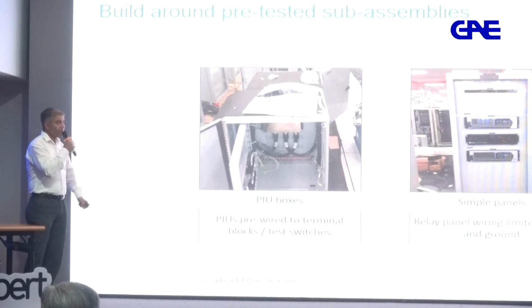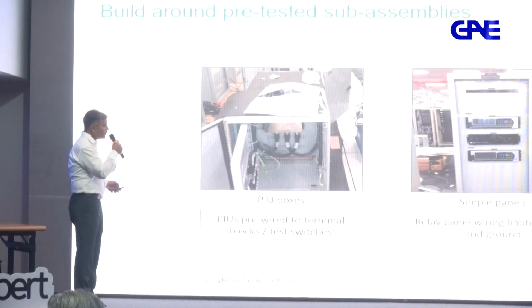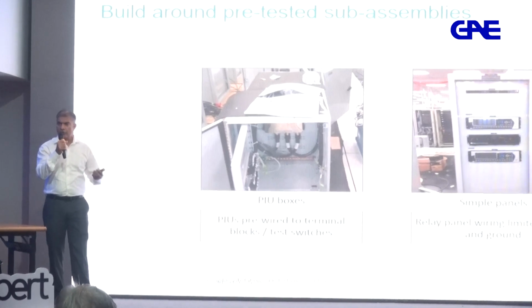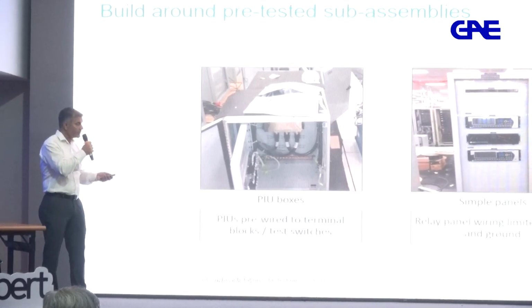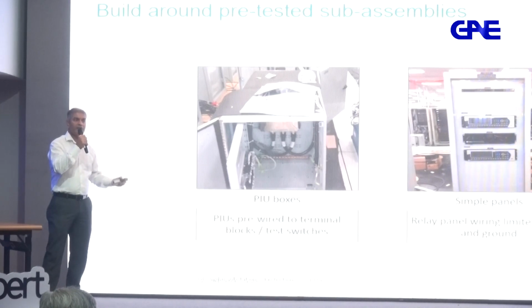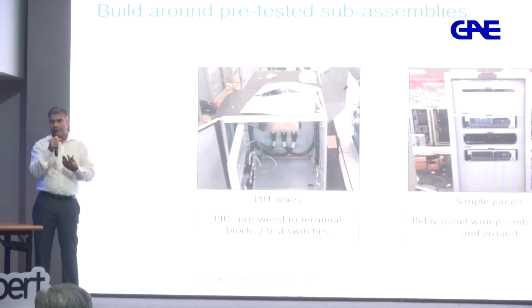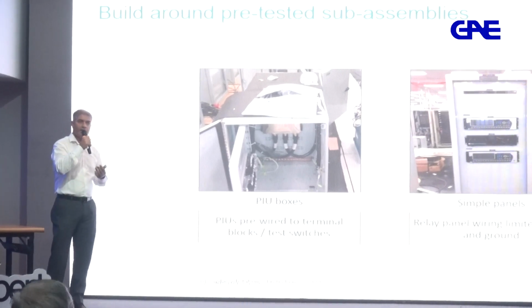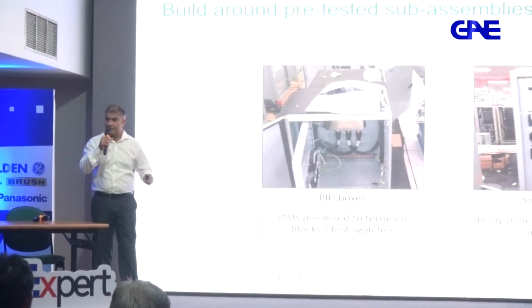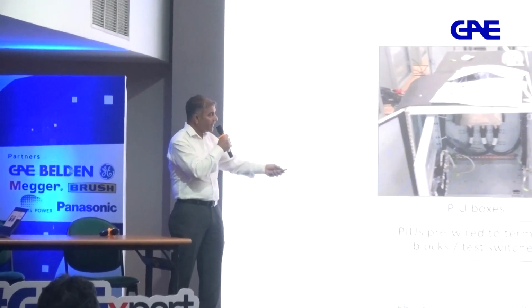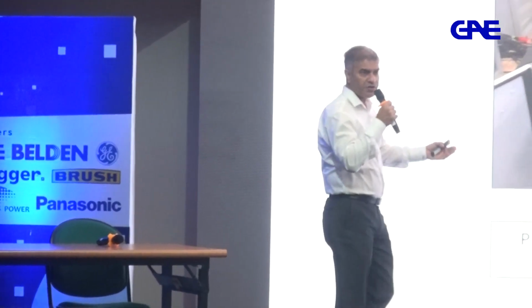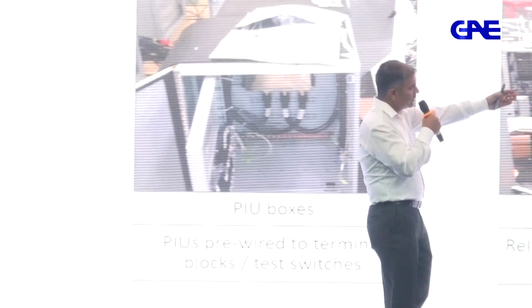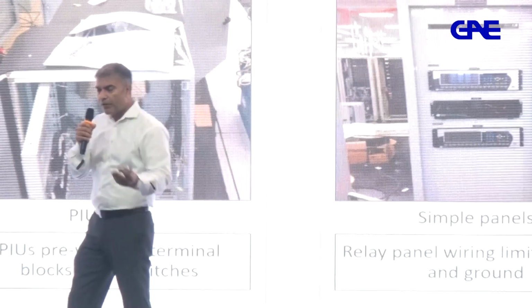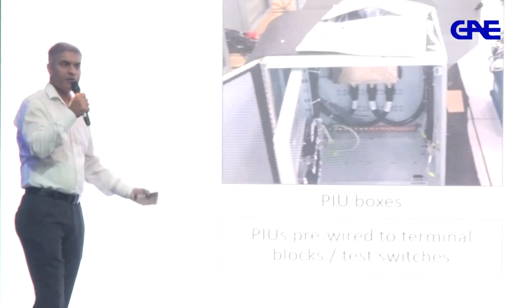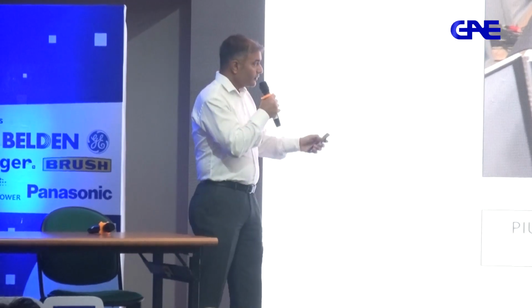Build around pre-tested sub-assemblies, right? Okay. So when you have an outdoor kiosk or a panel with a merging unit or process interface unit, it can be pre-tested in a factory. So when it comes completely tested from a factory, you don't need to spend a lot of time in commissioning at site, right? Simple panels, because now the panels don't have much wiring. They don't have wiring at all. This panel has only power supply and fiber optic. So what is there to test? Really nothing, right? So panels can be simple.